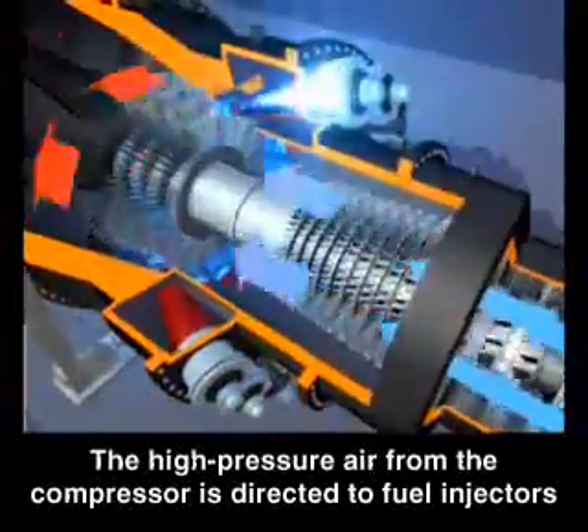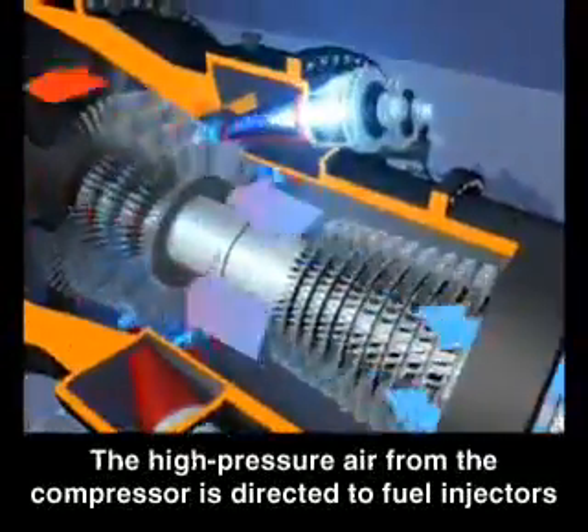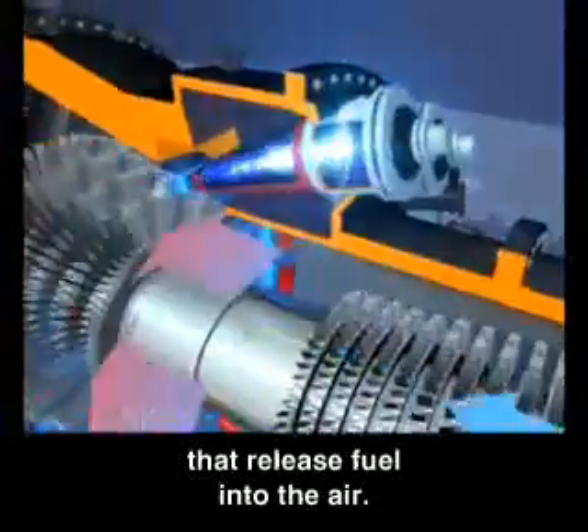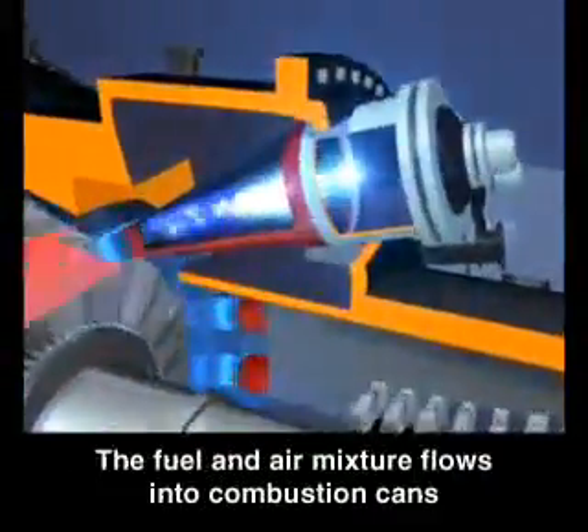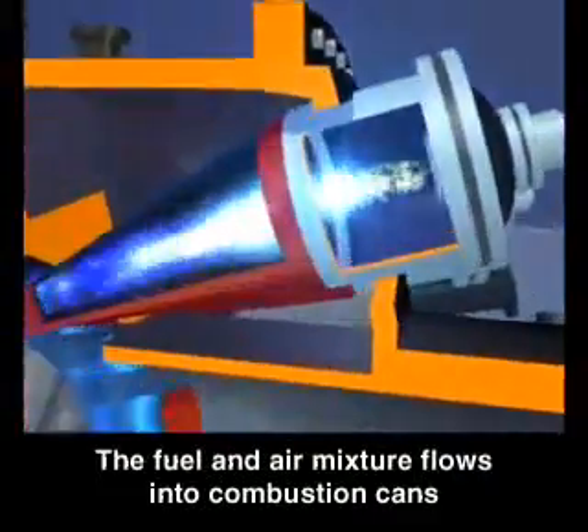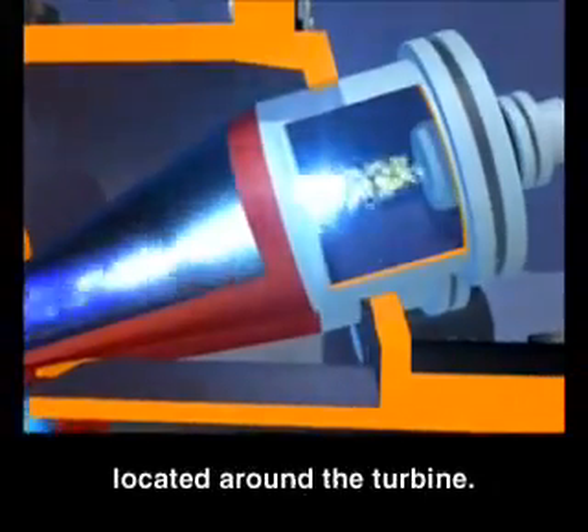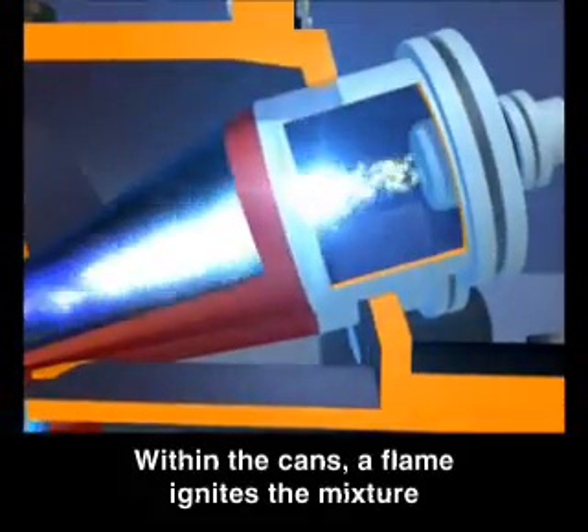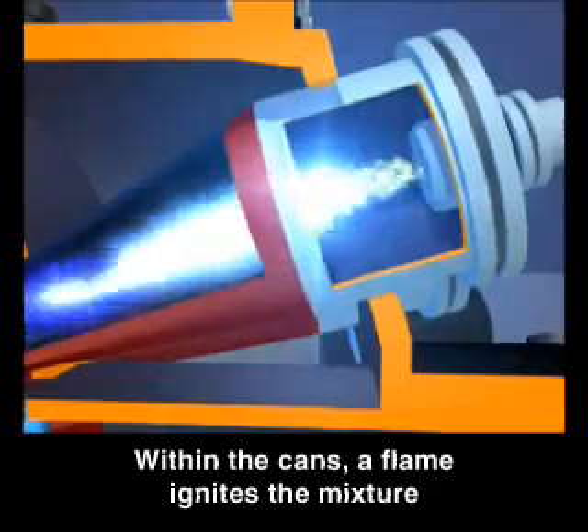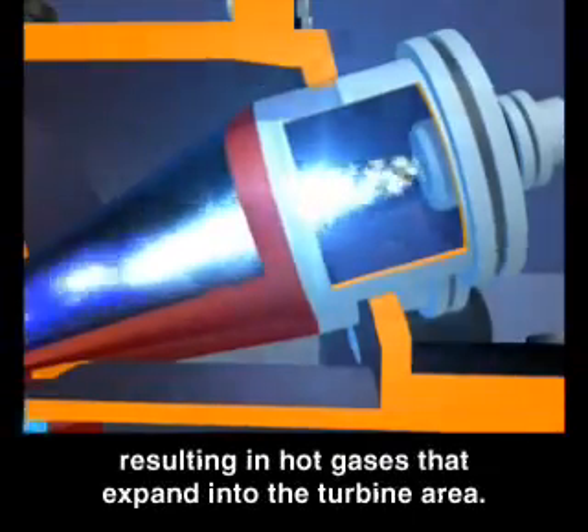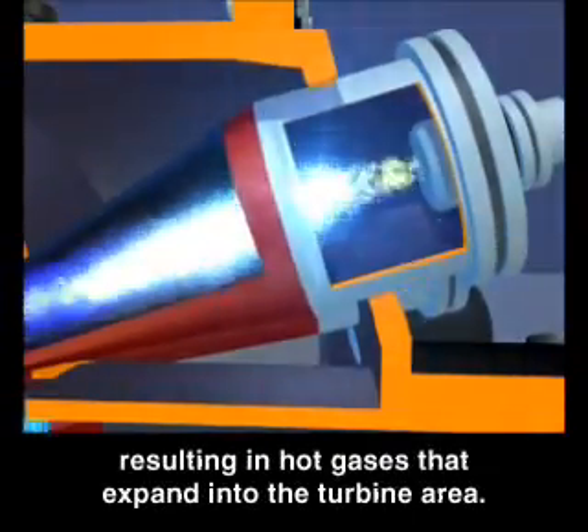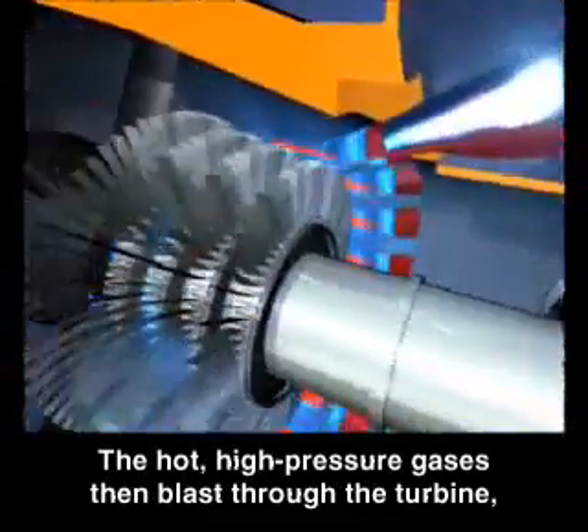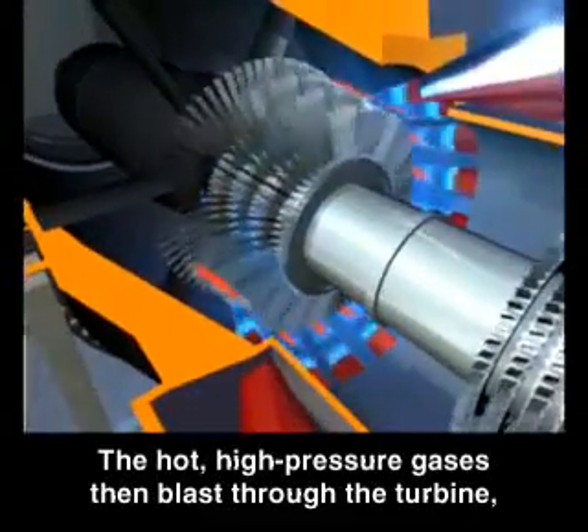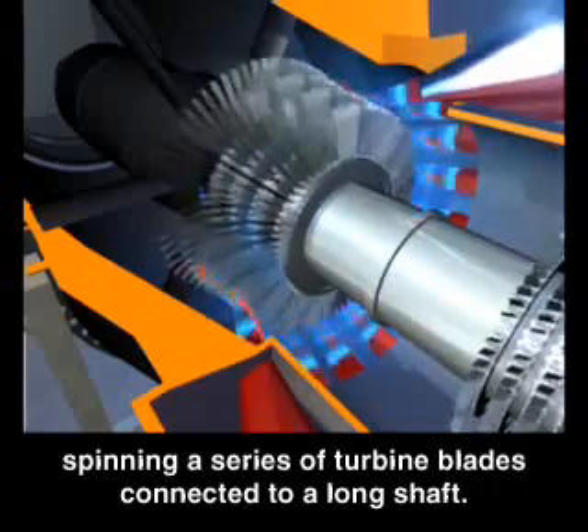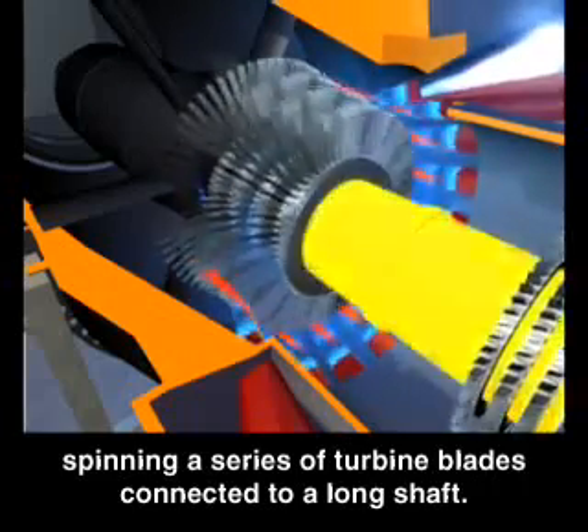The high-pressure air from the compressor is directed to fuel injectors that release fuel into the air. The fuel and air mixture flows into combustion cans located around the turbine. Within the cans, a flame ignites the mixture, resulting in hot gases that expand into the turbine area. The hot, high-pressure gases then blast through the turbine, spinning a series of turbine blades connected to a long shaft.